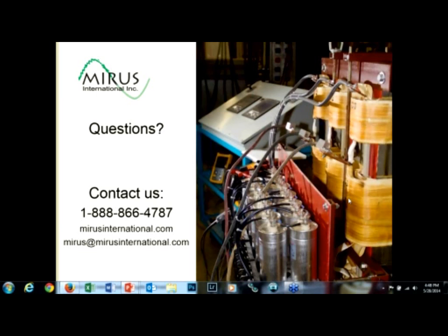Okay, let's see. We've got a question on how the cost of a lineator compares to a 12-pulse or 18-pulse system. Typically, we see the combination of a lineator with a 6-pulse variable speed drive to be about 25 to 30% less expensive than a comparably sized 12-pulse or 18-pulse system when you include the transformer that's required for the phase shifting.